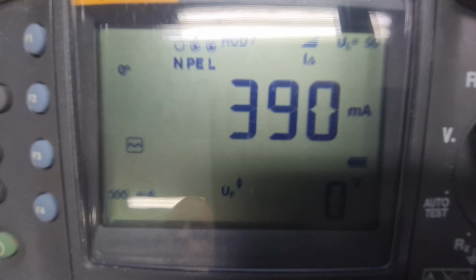Now, typically leakage currents are very complex waves, but due to the problem of having DC ripple or DC leakage currents, the RCDs may not function as desired. So through this simple video, we observe that there is a significant difference in performance for these old type RCDs, and it is highly recommended to convert such systems to modern type A RCDs. Obviously, the type A includes the safety protection for DC ripple currents, and the tripping times for these modern devices are in line with the regulations.